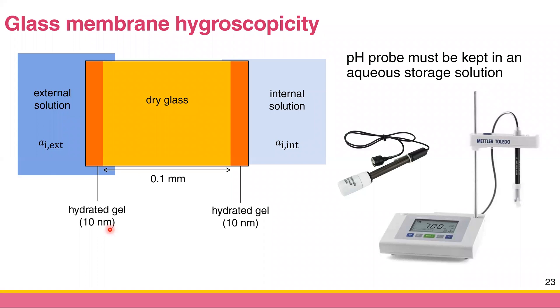Once you put the glass membrane in aqueous solution, hydration occurs, turning the glass membrane into something called a hydrated gel. That's why we say the glass membrane is hygroscopic — it absorbs water to become a gel. The orange-ish area in the diagram is the hydrated gel, and it has a very small thickness of only about 10 nanometers, compared to the dry glass which might be about 0.1 mm.